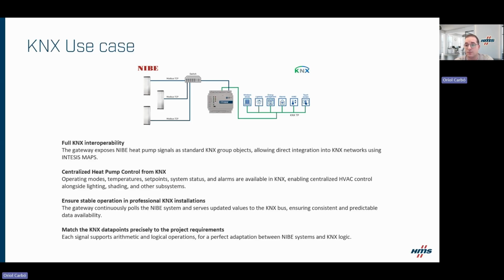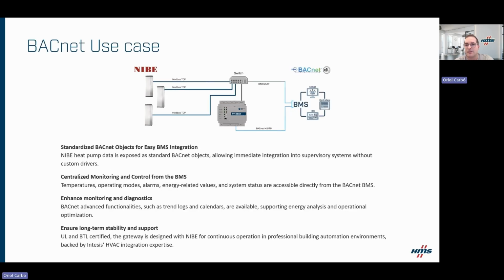And at the end, each signal supports arithmetic and logical operations, so you can match the points to the project requirements. And from the BACnet side, NIBE data is exposed as standardized BACnet objects, so integration into the BMS is straightforward without custom drivers. You get centralized monitoring and control directly from the BMS, plus advanced BACnet capabilities like trend logs and calendars for energy analysis. The certificates ensure long-term stability and support, with the protocol translator designed for continuous operation in professional environments, backed by Intesis HVAC integration experience.